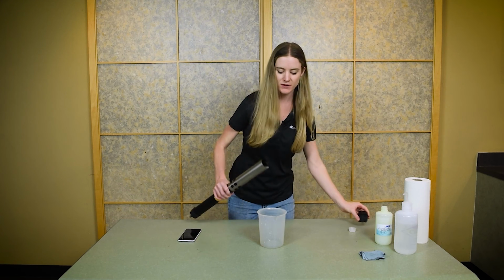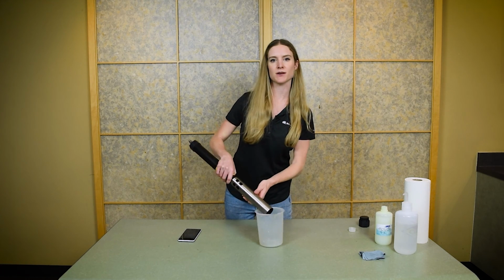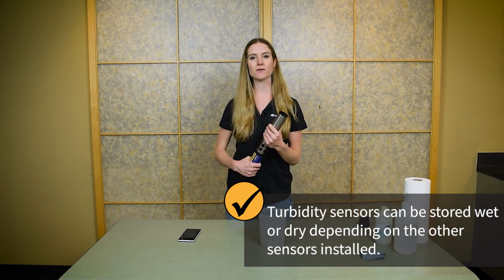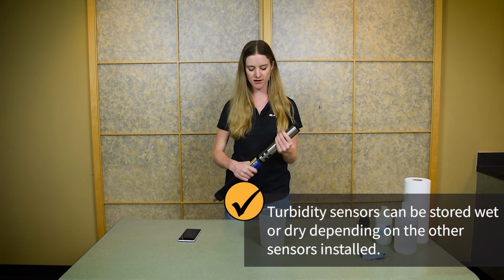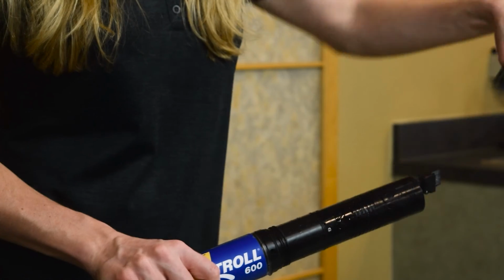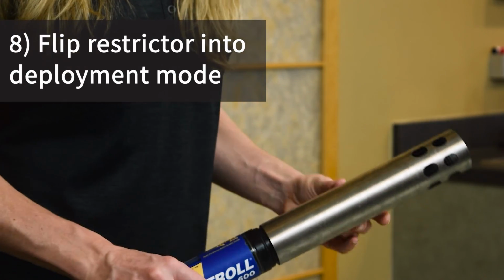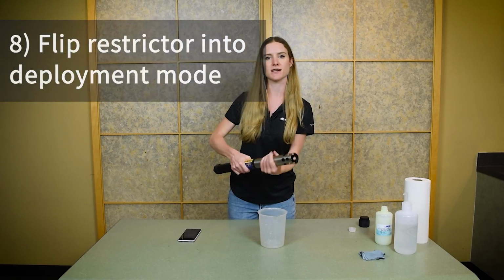Once the calibration is complete, your turbidity sensor is now ready to be deployed. Your turbidity sensor can be stored wet or dry, depending on what other sensors you have installed. When you're ready to deploy your instrument, don't forget to flip the restrictor back into deployment mode with the holes away from the center of the instrument.